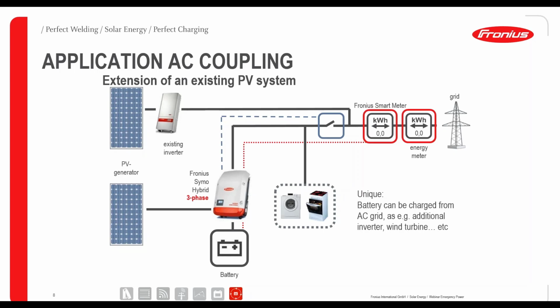So whenever you have a longer blackout, a few days, the battery will be recharged from the PV generator as well in this case. If I would have no PV generator on the Symo Hybrid, I would have no chance to charge the battery from PV, because the backup switch is switched off. There's no power flow from the existing inverter to the battery anymore, and then of course you can use your battery capacity only as long as you have some kind of charging in the battery. So that's the basic idea behind our system.